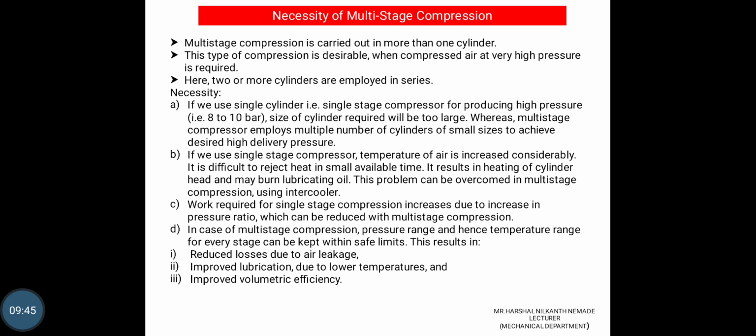Necessity of multi-stage compression. Multi-stage compression is carried out in more than one cylinder. This type of compression is desirable when compression of air to very high pressure is required. Here, two or more cylinders are employed in series. Okay, necessity: if we use a single cylinder, that is a single stage compressor, for producing a high pressure of 8 to 10 bar, the size of the cylinder required will be too large, whereas a multi-stage compressor employs multiple cylinders of small size to achieve the desired delivery pressure.